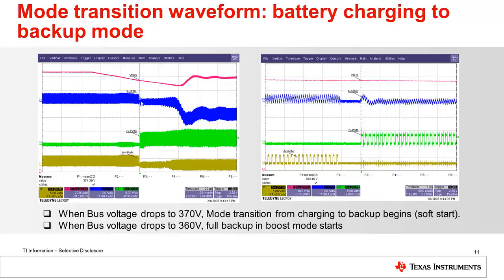Once into the backup mode, the system stays in soft start until the point that the DC bus voltage falls to 360 volts. At this point, the system moves into a full boost power mode and tries to regulate the DC bus voltage to 370 volts.